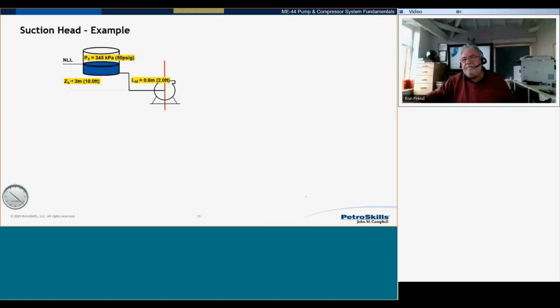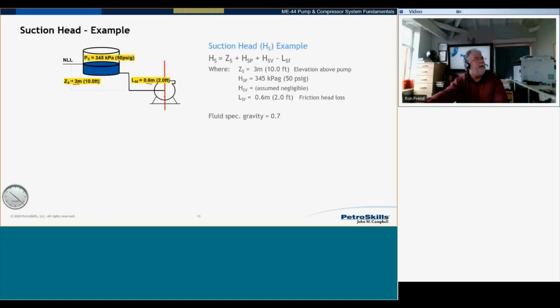So let's do an example. All right, in this example, we've got a suction tank, 50 psi, 345 kPa. We've got 3 meters of head from the liquid level to the pump suction, and I've got friction losses of 0.6 meters. Now that's our formula that we're going to work with. We've got all the information here that we need. We're also being given the specific gravity, which is 0.7. I need that because some of these things are in pressure, some of them are in head, and I want everything to be in terms of head.